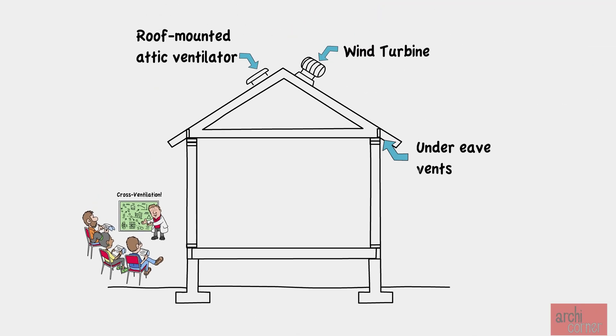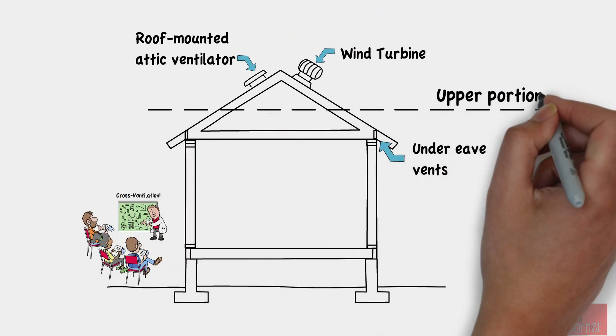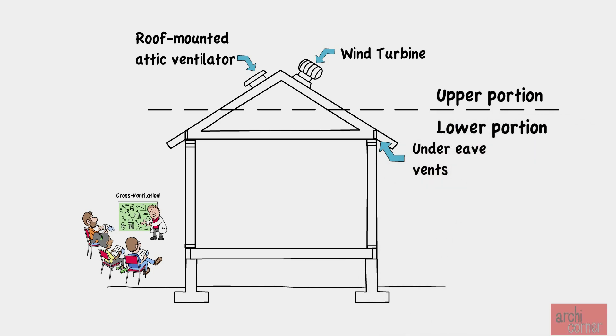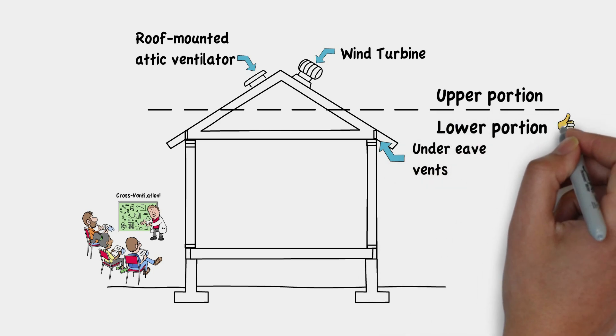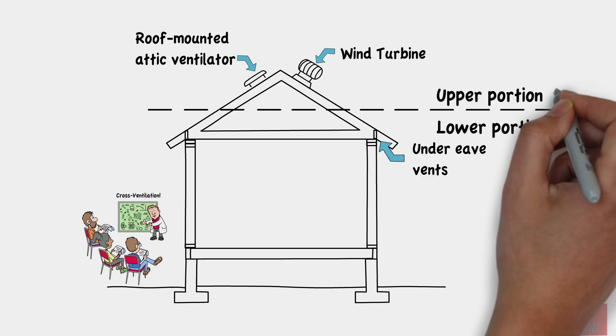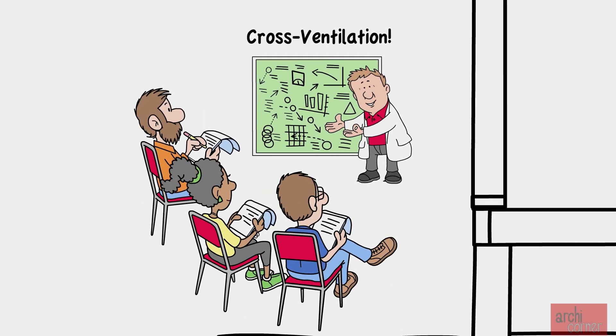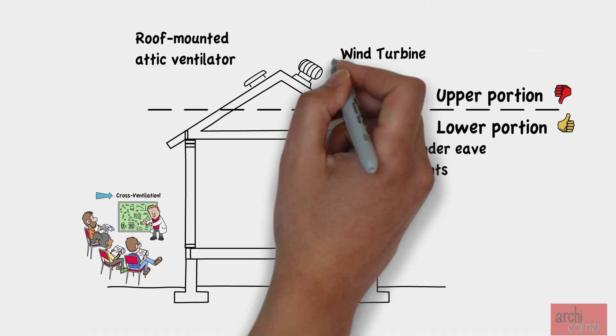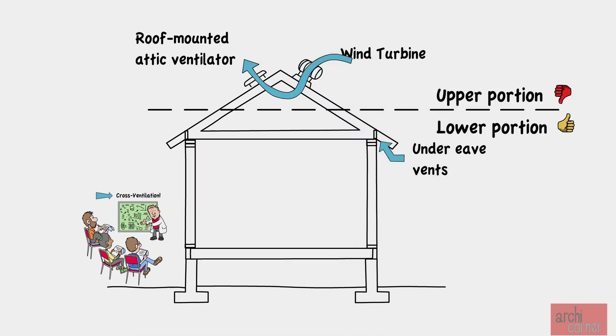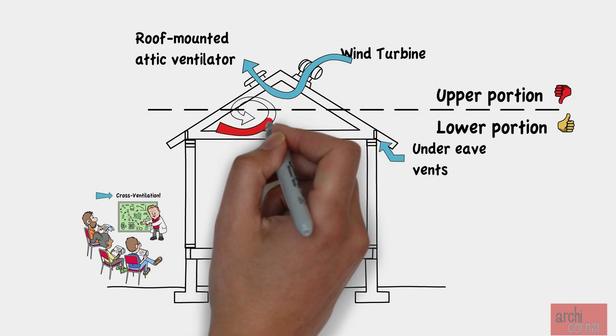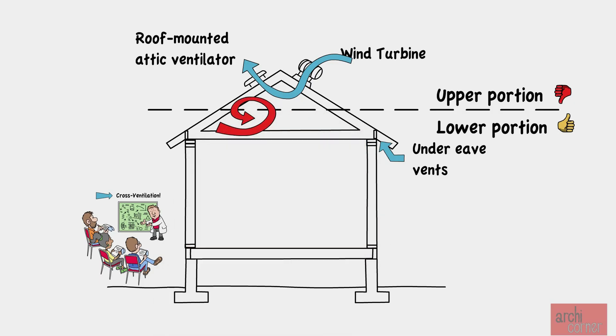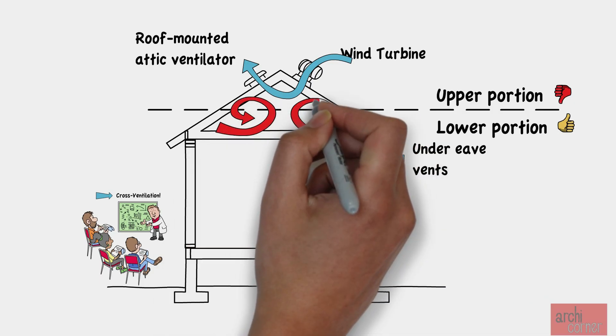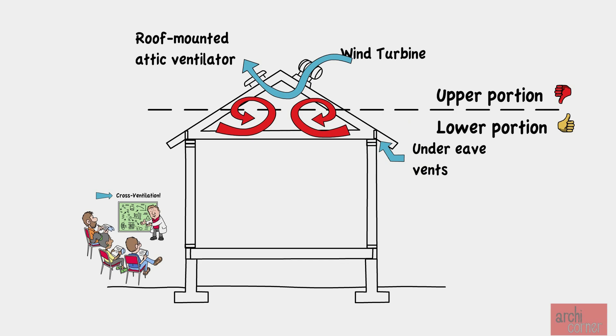Let's divide the portion of the roof into the upper portion and the lower portion. While it may be okay to have all or most of the ventilation on the lower portion, you do not want to have ventilation only on the upper portion. The reason is that you want cross ventilation throughout the entire roof. The code sections related to vented roofs basically provide two venting options.